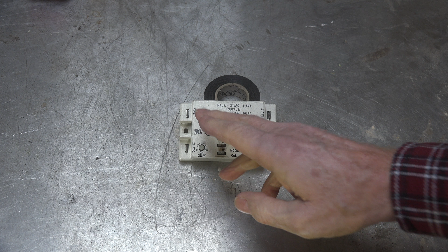And if you put it to 240 and it gets to where it blows cold air before it shuts off, that's objectionable to a lot of people. Start out with it at the dots on those, and if you're blowing cold air after the burner shuts off, then you drop it down a little bit. And if you still have plenty of warm air, be sure to clear all that heat out of the ductwork. It's a little more efficient, so you run it longer. That's about it. Nothing special on those things. That's it on this one.